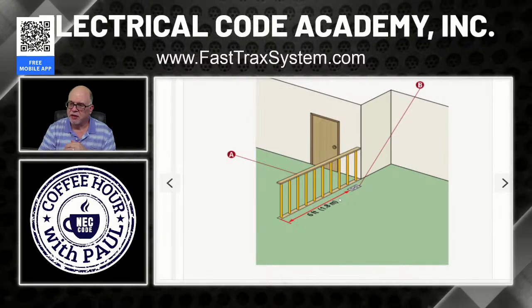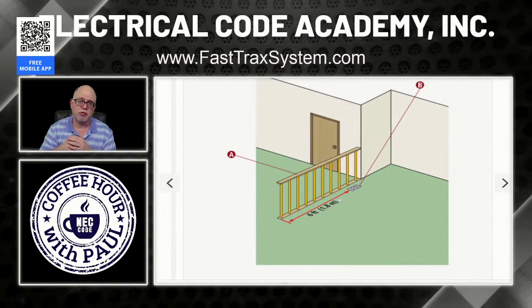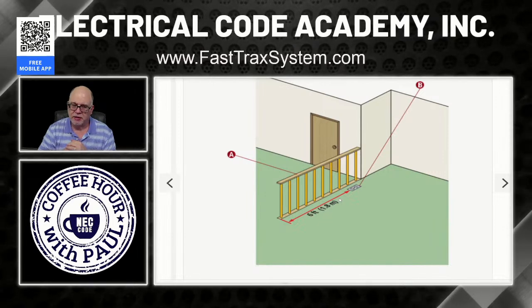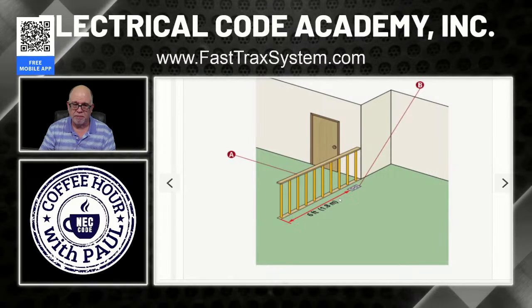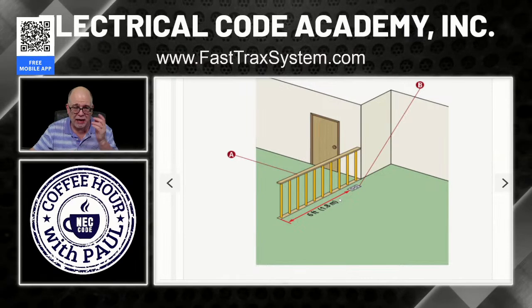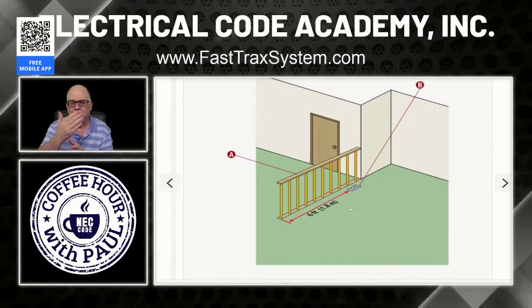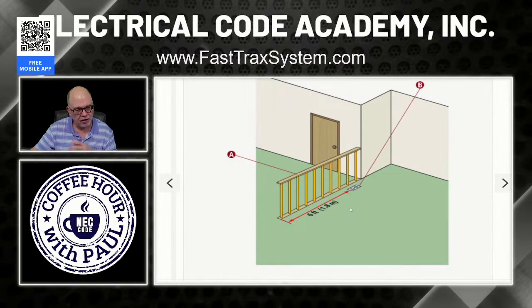Now, in this case, the customers were going crazy because it was a concrete floor and I still needed those receptacles. And so they had to put receptacles in the floor, and they were special floor type boxes, because they were in the concrete and they were expensive, but they had to have them because I had to have those receptacles. And that receptacle had to be within what? 18 inches of the wall in order to qualify to meet the wall space requirement. Okay? So it is okay to put them in the floor. Just, again, you gotta install them within 18 inches of the wall to qualify.